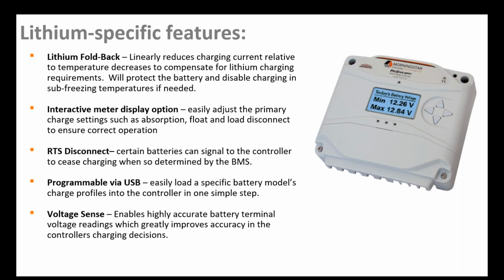And then one other very useful feature for accurate charging in general is to utilize the voltage sense capability, which is not a standard feature on many charge controllers. Morningstar prides itself in taking extra good care of the batteries that are such a precious investment for our end users. Measuring the voltage directly on the battery terminals and accounting for any voltage drop over a wiring distance between the controller and the battery is the best way to make sure it's getting adequately charged. So many of those features will prove to be useful when working with lithium.